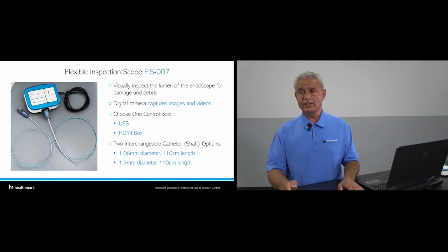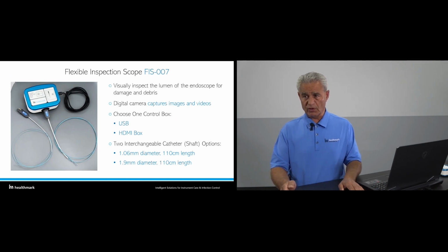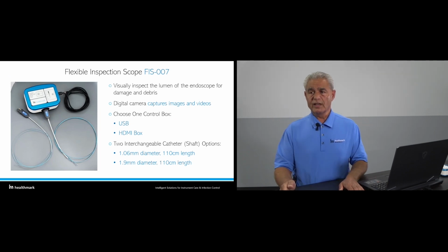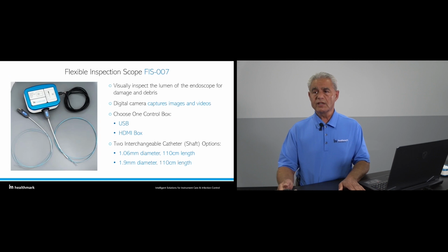You can use the USB box, which records videos and pictures for further review, or a HDMI box which is just for review, if you do not need the USB or software. Some of our customers have difficulty adding software to their computers, so they can use the HDMI. And with the various sizes of endoscopes, some are okay with a 1.9 millimeter diameter scope, but for smaller diameter lumens we have a 1.06 millimeter diameter.